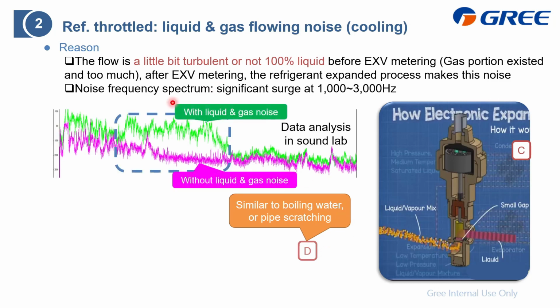We also tested this in our sound lab. This is the noise frequency spectrum with liquid and gas noise, the green color curve, and this is with the refrigerant ensured to be 100% liquid when doing the metering. We find that it is different, and just here, at 1000 to 3000 Hz, the frequency spectrum makes the noise.